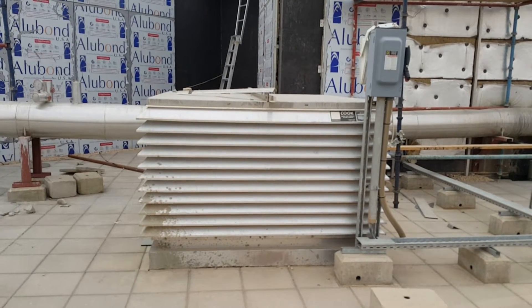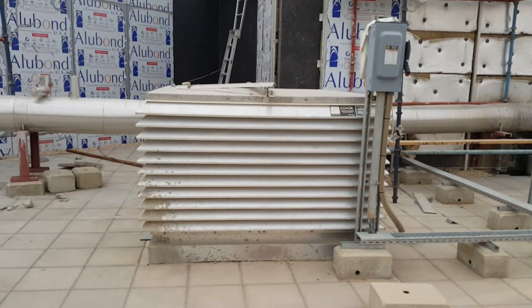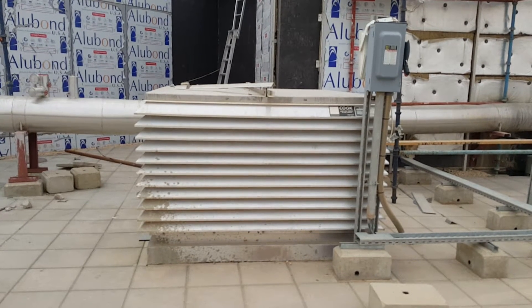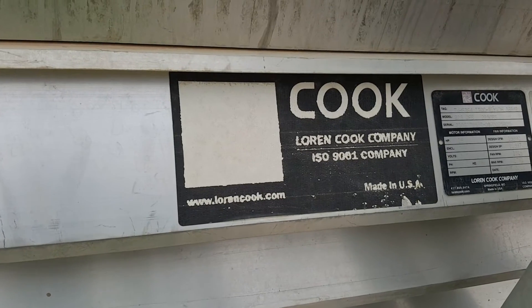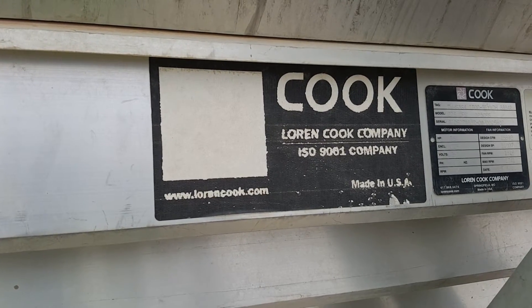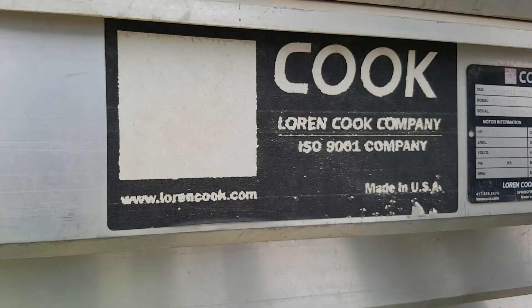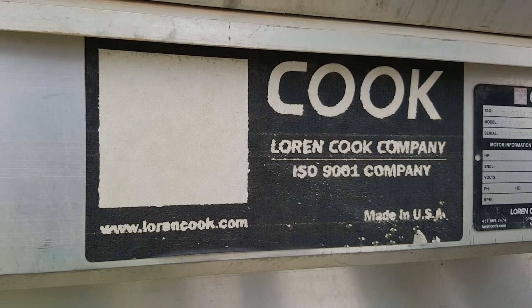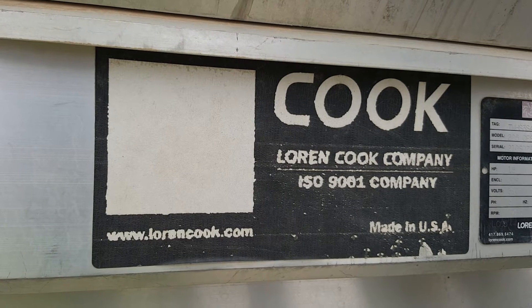I will explain the RPM and CFM. This is a Proxima 27-story building, so we pressurize all the stairs with this pressurization fan. You can see this is a Cook company fan, made in USA, ISO 9001 certified and also UL certified. This is a Proxima 15,892 CFM and the RPM speed is 725 to 741.